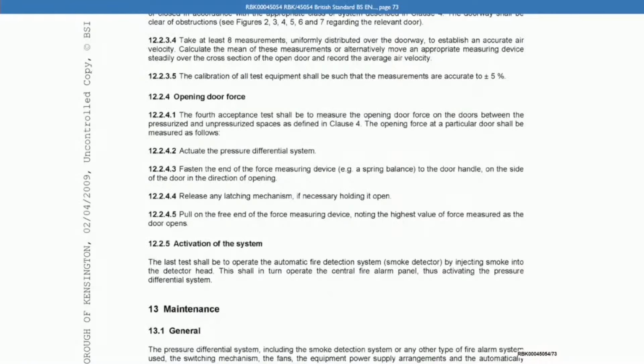Now, the fourth acceptance test is the opening door force. We can see that if we go back to the British Standard BS 12101-6, page 73, and we look at paragraph 12.2.4, with the heading opening door force. And if we look below that, it says the fourth acceptance test shall be to measure the opening door force on the doors between the pressurised and unpressurised spaces as defined in clause 4. The opening force at a particular door shall be measured as follows.